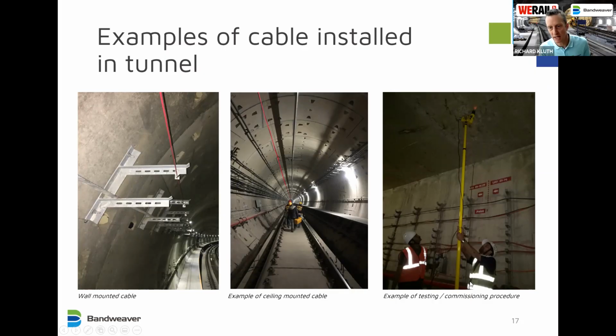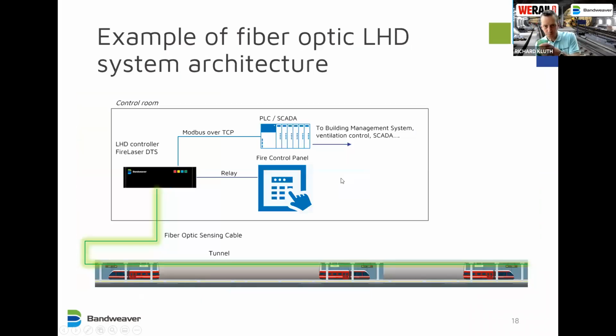Here they're using a heat source on a pole to simulate a fire event, which, as I said, in this case is used in commissioning, but is also used on the regular checks that are carried out throughout the lifetime of the project. In terms of how the system integrates with the fire control system, there's essentially two methods for this. So the simplest is electrical relays to the fire control panel. So each alarm has an electrical relay which would correspond to the zones in the fire control panel, which would trigger in the event of an alarm.